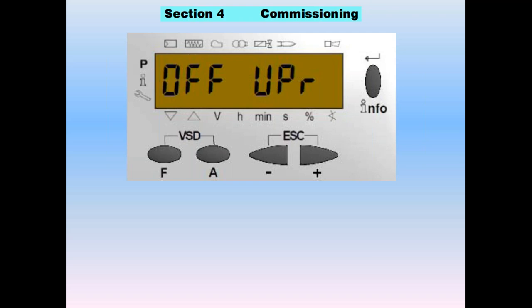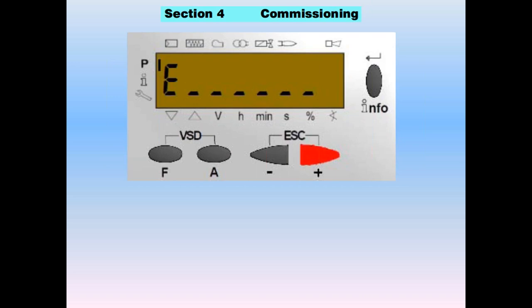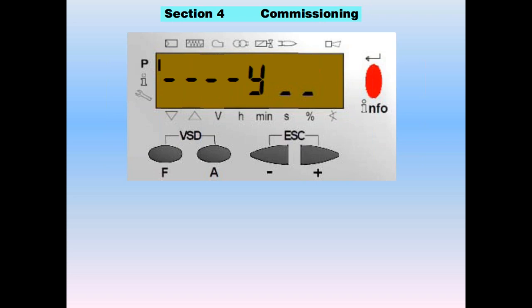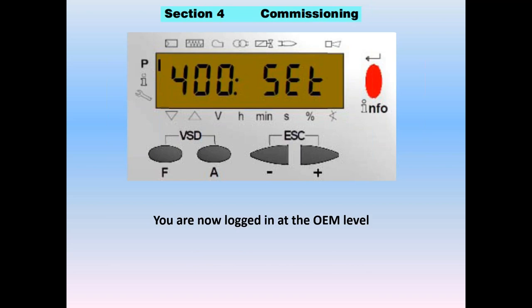Here's our burner. We have 'off unprogrammed' in front of us. Push the F and A keys together and release — the screen will flash 'code' and come up with blanks ready for you to enter the code. By pushing plus or minus, you can dial up the code — in this case, E for 'entry.' Hit enter, then enter N, T, R, Y. When all elements are in, hit enter one more time. It will flash 'parameters' and go into the 400 set.